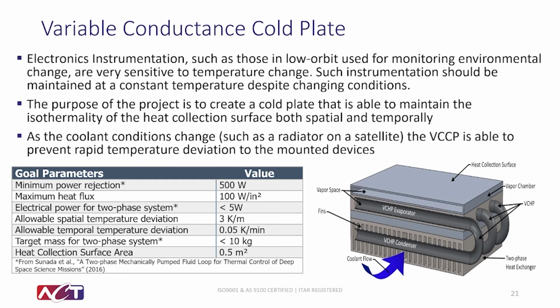On the bottom right, we can see a concept image of the variable conductance cold plate. Please note that the features are exaggerated just to make it easier to see. Starting at the top, we see the heat collection surface where the electronics would be mounted and generating heat. Beneath that is a vapor chamber, which consists of a large vapor space. This vapor chamber helps spread out the heat, and due to the nature of the two-phase working fluid held at saturation within the chamber, it provides a highly isothermal surface.